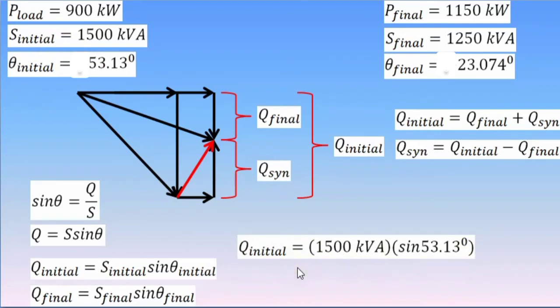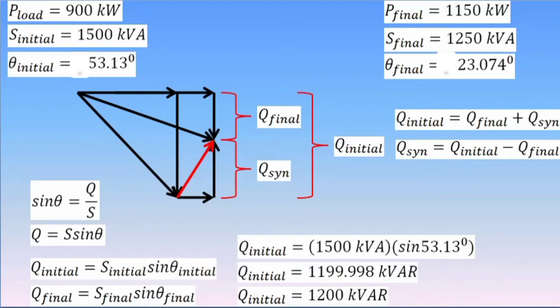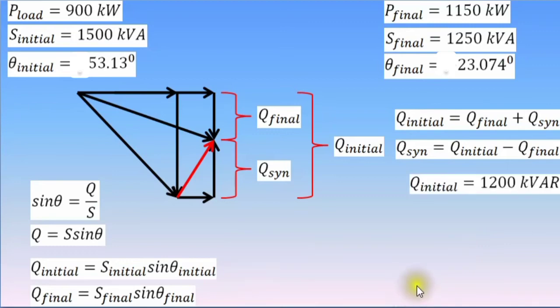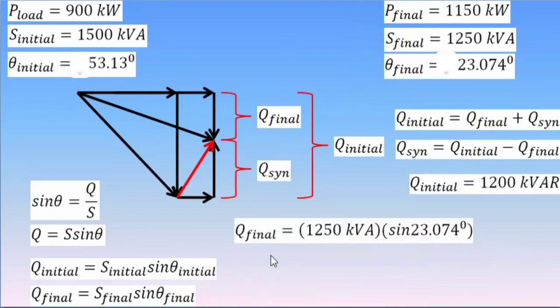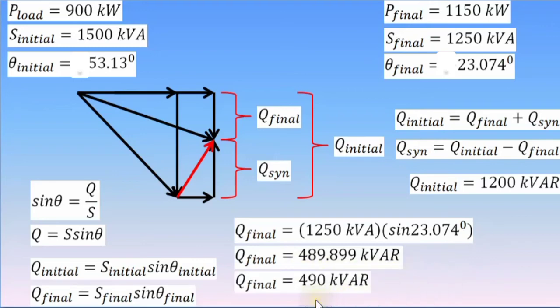To solve for the reactive power of the initial condition, substitute the values. Initial reactive power equals 1,500 kVA times sine 53.13 degrees. Its value is 1,199.998 kVAR, or this could be rounded off to 1,200 kVAR. Now to solve for the reactive power of the final condition, substitute the values. Final reactive power equals 1,250 kVA times sine 23.074, that is 489.899 kVAR, or this could be rounded off to 490 kVAR.